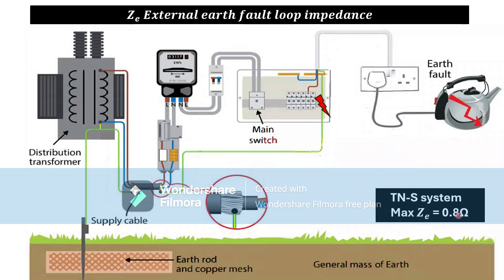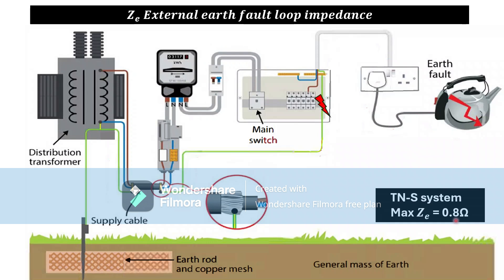The maximum Ze for a TN-S system is 0.8 ohms, so our value should be below 0.8. If it is greater than 0.8, we have to inform the DNO regarding this situation.